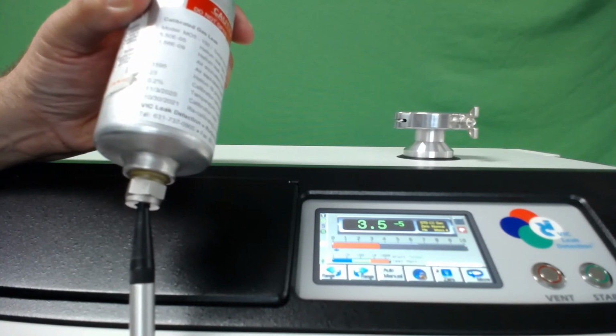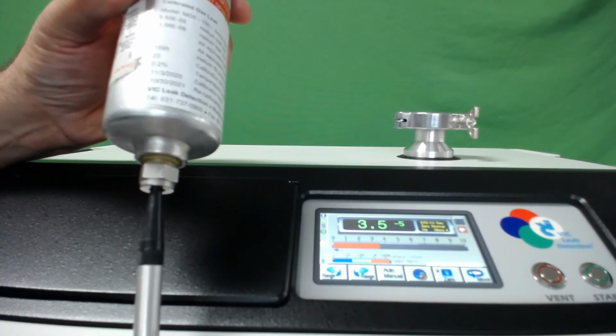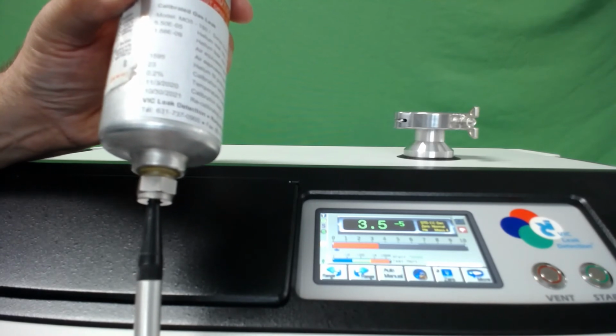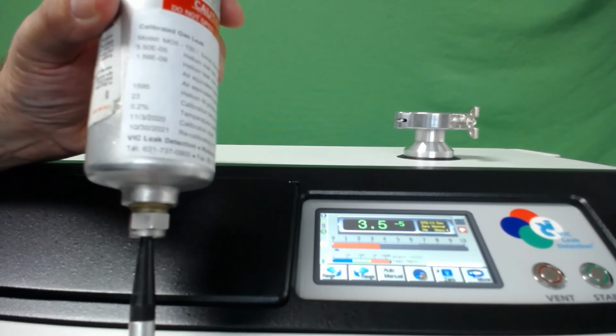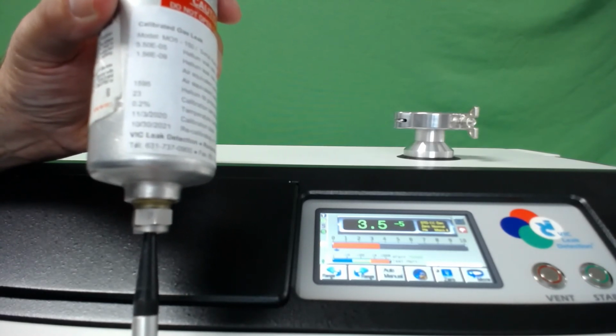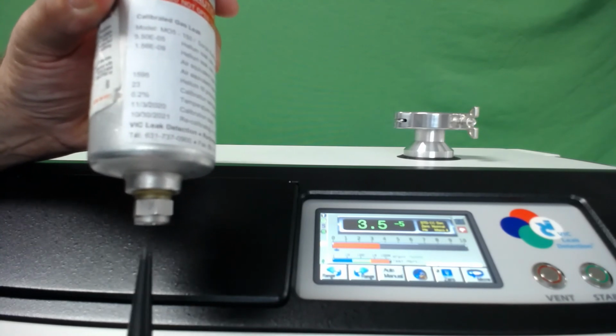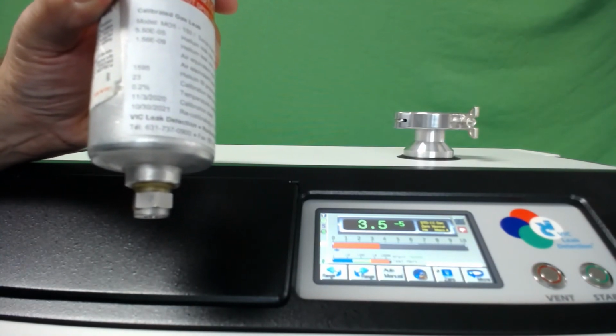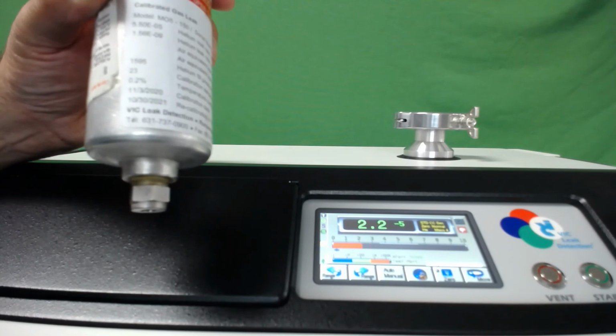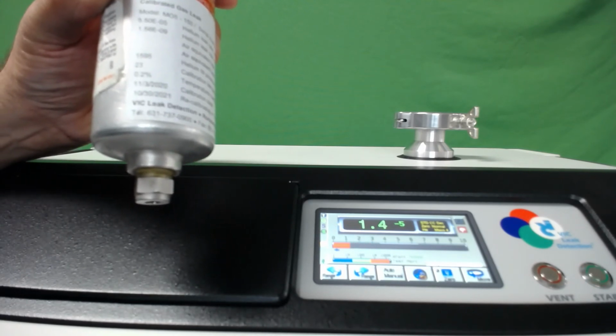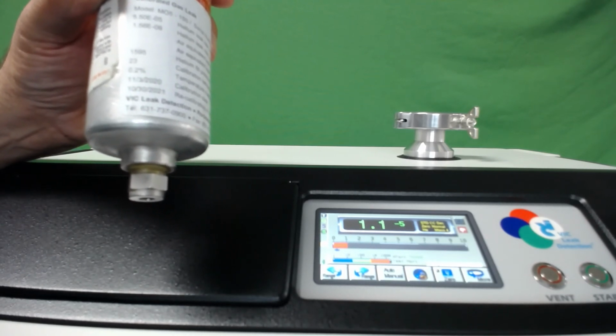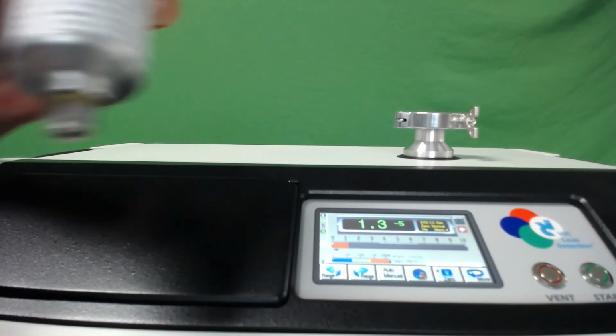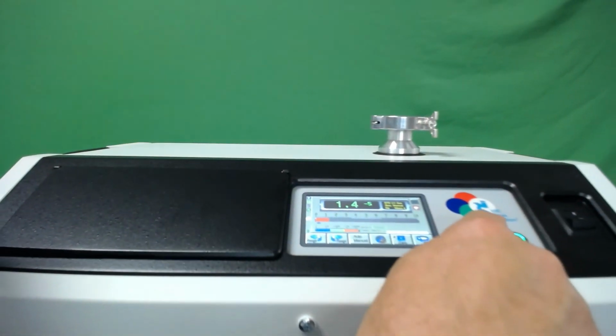The MS-40GT is also equipped with a Sniffer Probe function. Here you can see the machine measuring an atmospheric discharge leak at 3.5 times 10 to the minus 5. When the probe is removed, you can see the leak rate immediately begins to drop. The Sniffer Probe is attached to the rear of the instrument, and to take the machine out of sniffing mode, you simply press the vent button.